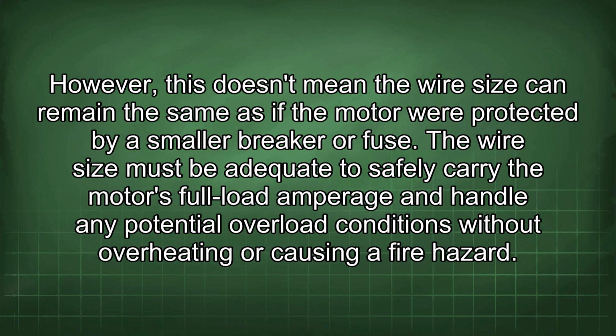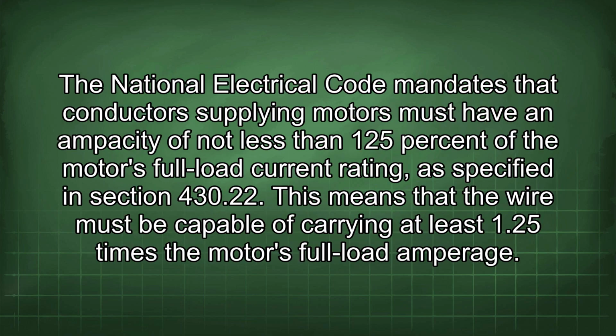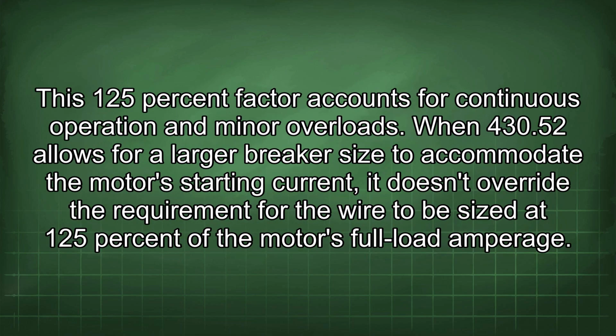The wire size must be adequate to safely carry the motor's full load amperage and handle any potential overload conditions without overheating or causing a fire hazard. The National Electrical Code mandates that conductors supplying motors must have an ampacity of not less than 125% of the motor's full load current rating, as specified in Section 430.22. This means that the wire must be capable of carrying at least 1.25 times the motor's full load amperage. This 125% factor accounts for continuous operation and minor overloads. When 430.52 allows for a larger breaker size to accommodate the motor's starting current, it doesn't override the requirement for the wire to be sized at 125% of the motor's full load amperage.